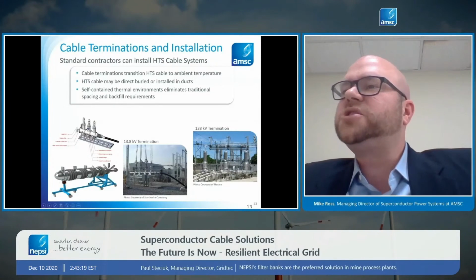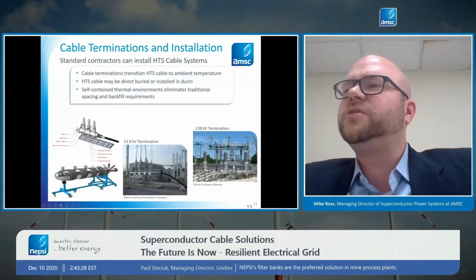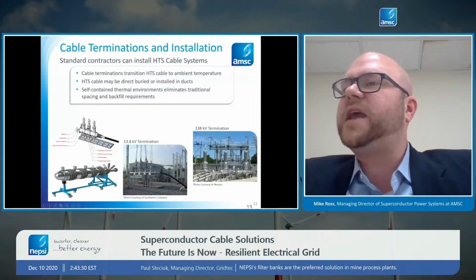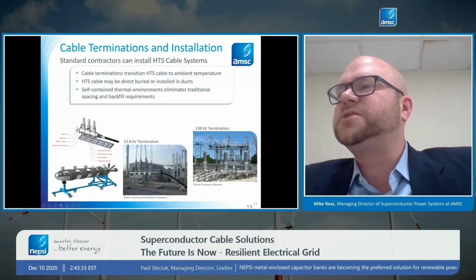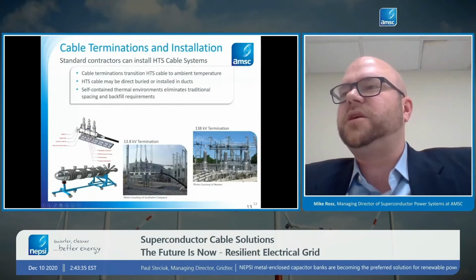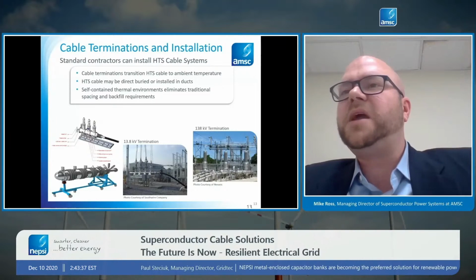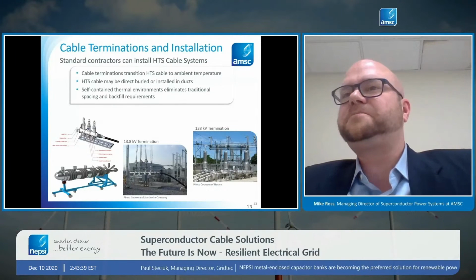When you go to transmission voltages, 69 kV and above, often we're using single phase terminations. So these are what you're looking at here. This is 138 kV terminations. And I have another slide that looks a little bit closer at this. So those are the main components of the system.